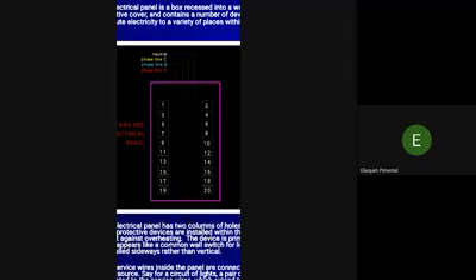Gets nyo guys? Circuit number 1 and circuit number 2 should have the same ampere. Ampere is the amount, the volume of electricity, because you have 7 outlets na tig 200, so it's 1,400 wattage. So the ampere capacity of the breaker, the volume of electricity, should handle 1,400 wattage. Meaning 220 times 1,400 is the ampere. Or divide. I will show you the formula. Not now. Baka ma-confuse kayo.